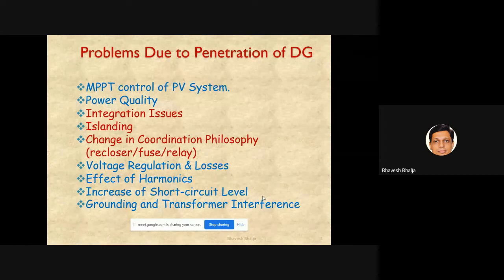This is going to play an important role when you connect the DG with the grid. Just a simple example: if I have done the grounding, and if I am doing some measurement based on zero sequence current with a delta connection, then you know that the zero sequence current does not come out of the delta winding, it remains circulated within it. So grounding plays an important role.